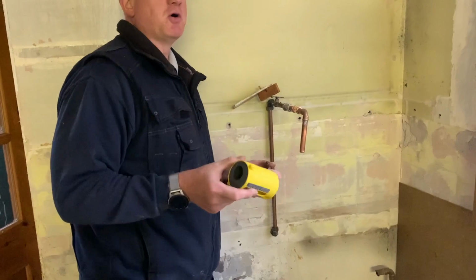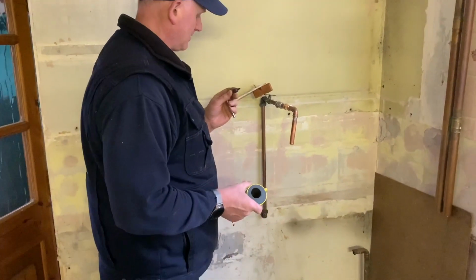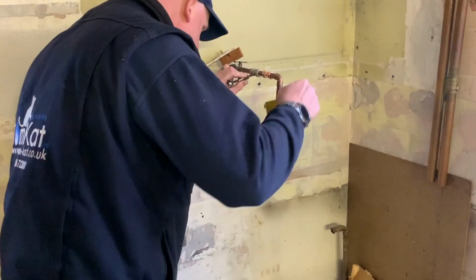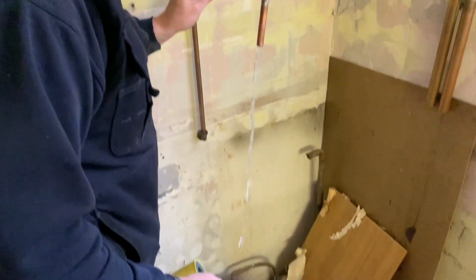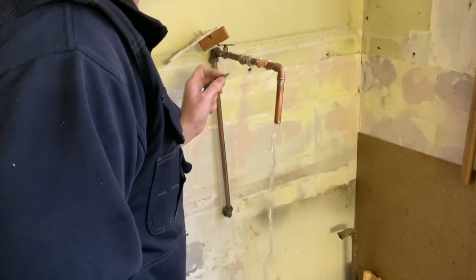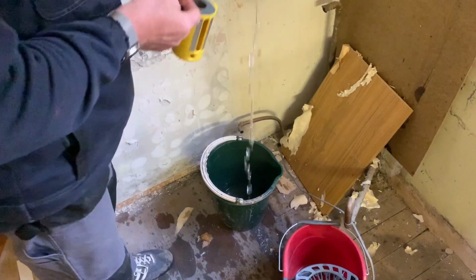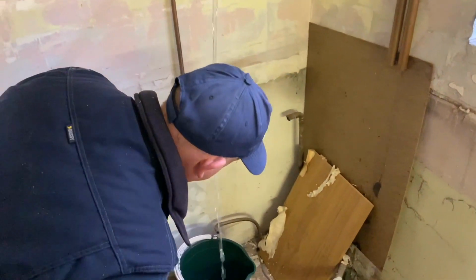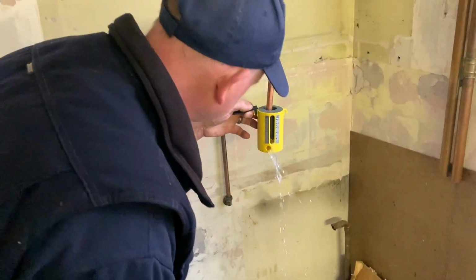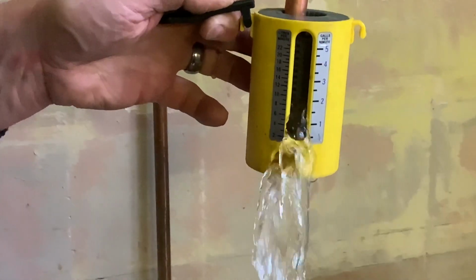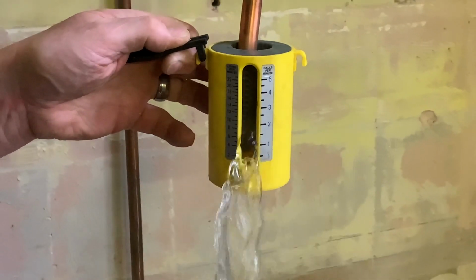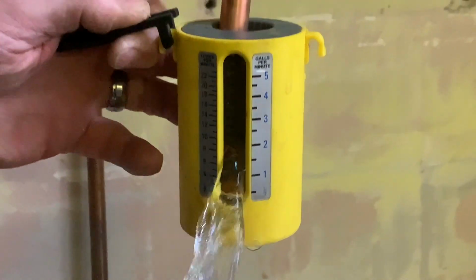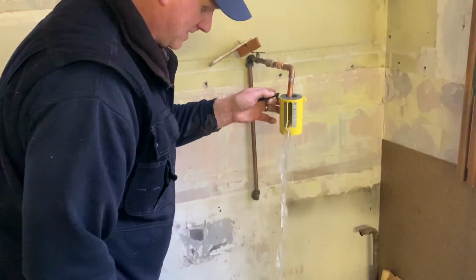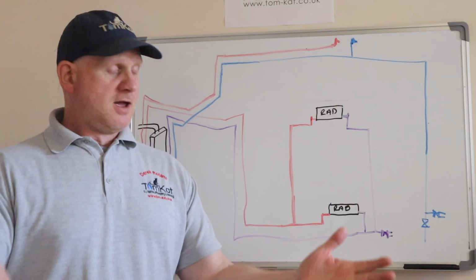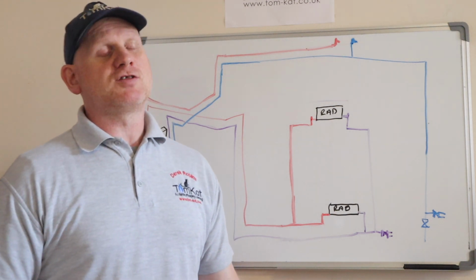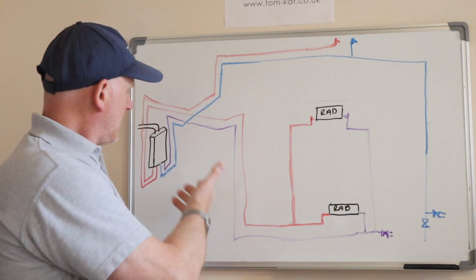So, with no hot taps in the house because the builder's ripped it all out, what we've got to do is, this is what we've made up to test the hot water flow rate. Which isn't very fast. Good job. So that's the flow rate. What's it reading, Tom? About 8. There you go. All we got to do now is get the temperature. And that's how easy it is to convert a gravity hot water pump central heating into a combi boiler and a fully pumped system.